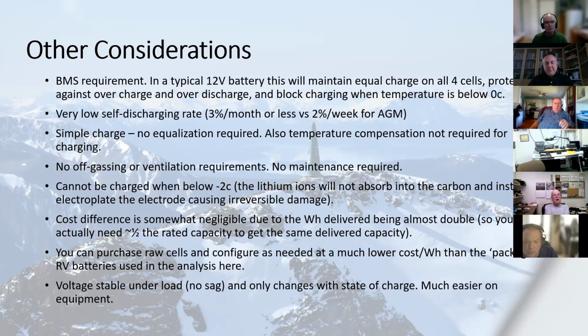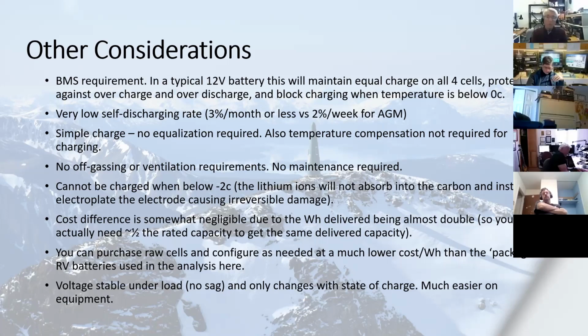You might get away with a very low amount of current for a short period of time when it's colder than -2 Celsius, but essentially the batteries are destroyed if you attempt charging them when colder than that. There are some ways of mitigating that. There are quite a few manufacturers now producing packaged batteries with heating elements in them that will divert charge energy to heating plates until they're up to enough temperature that they can accept the charge, and then they begin charging. So there are ways of handling that.